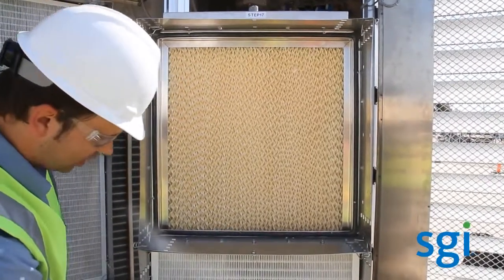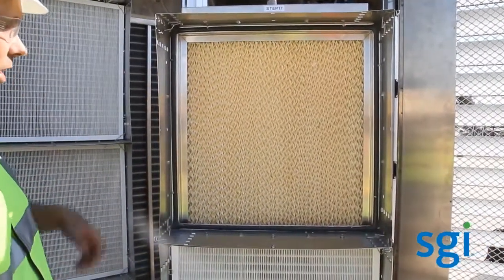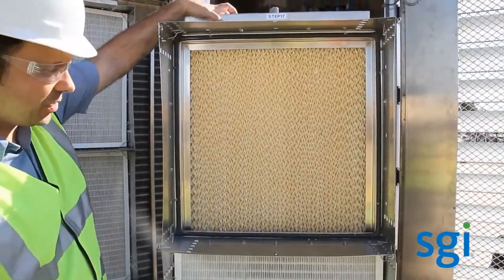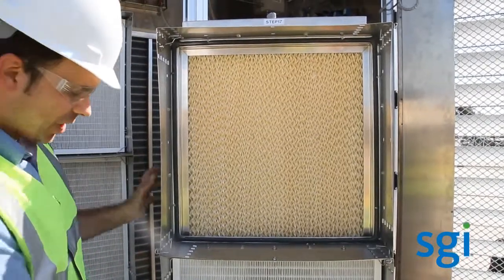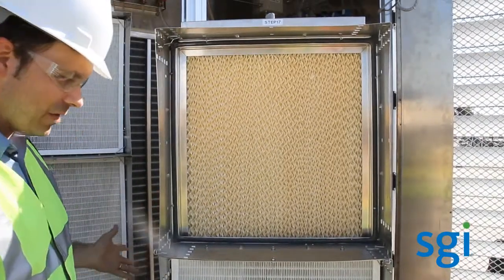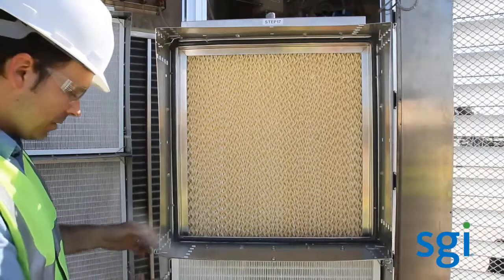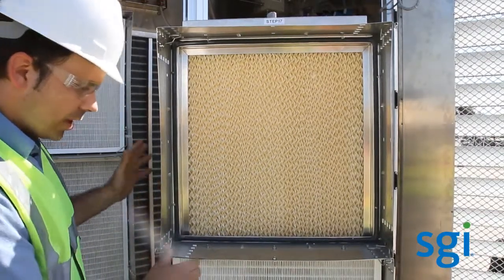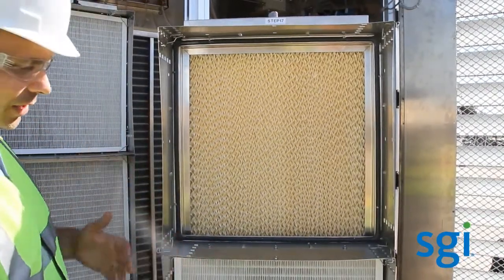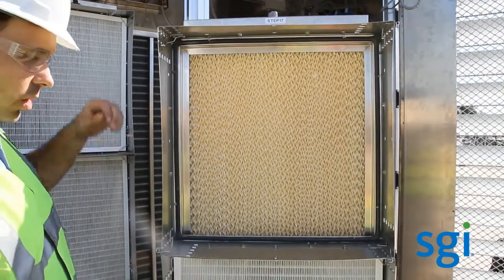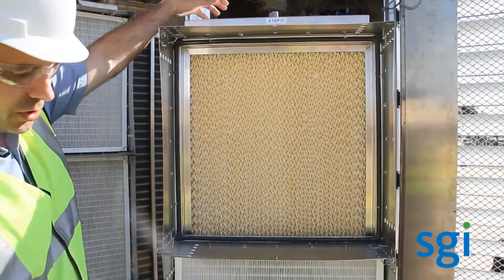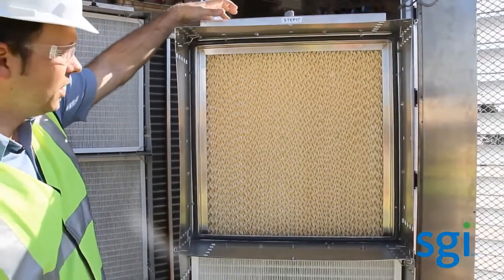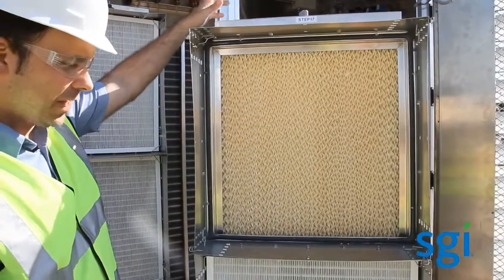You have the filters that come in and out - you saw how simple that was. The evaporative media actually pops out of the top. This is a lightweight aluminum section. Again, everything in this unit is high-grade aluminum and robust. Each section comes out and can be replaced as a whole unit, or during maintenance, even critical maintenance, popped out and replaced. That can be done on site.